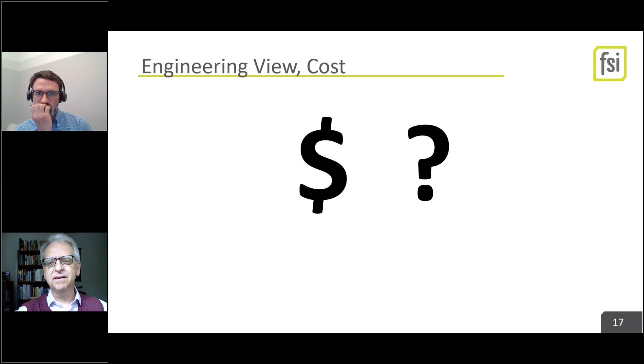Let me mention what was alluded to a minute ago: PTACs and PTHPs, package terminal heat pumps, have a U value of 0.5, as opposed to the 0.05 or so that the rest of your wall has. So we require that if you're going to use that PTAC system, you have calculated your wall insulation values and accommodated the fact that the 7 square feet of that opening for the PTAC is assigned a heat loss that's 10 times higher than the surrounding wall.